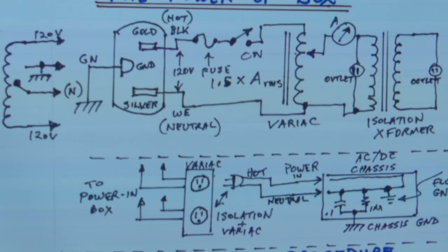Time over current. Yeah, it melts. The fuse melts. And when it melts, it's only associated with current and not an RMS value as such, because it's simply melting because of the heating power associated with a particular current that goes along there. So I've got it here rated at 1.5 times the current.